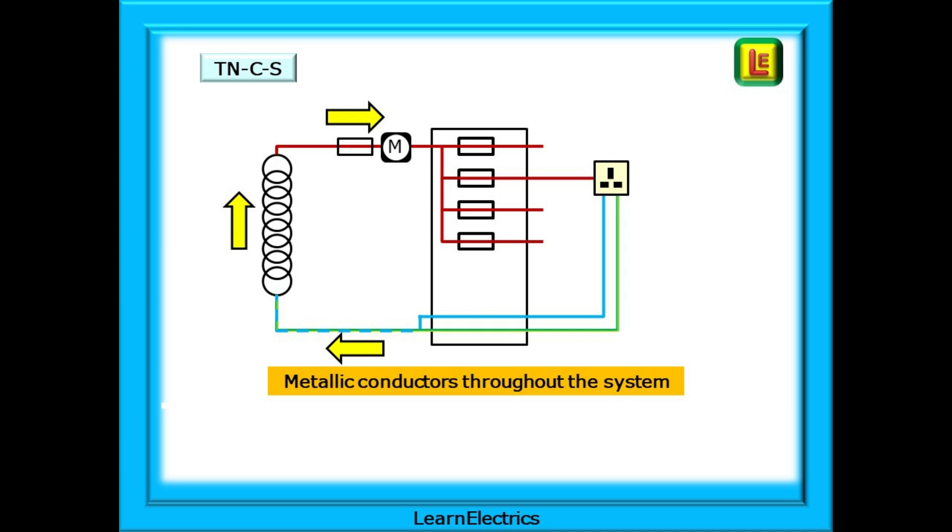The TNCS Earth Fault Path is similar to the earlier system. Fault current will flow along the Earth or CPC in the property, but at the consumer unit, it then flows along the combined cable back to the transformer. Through the transformer again, along the phase wire, through the fuses, and bang! The fuses blow, and make the installation safe. Just as before.